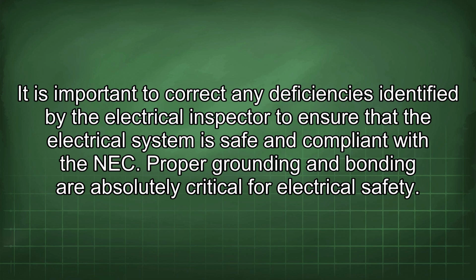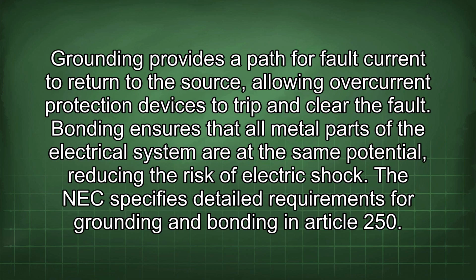Proper grounding and bonding are absolutely critical for electrical safety. Grounding provides a path for fault current to return to the source, allowing overcurrent protection devices to trip and clear the fault. Bonding ensures that all metal parts of the electrical system are at the same potential, reducing the risk of electric shock. The NEC specifies detailed requirements for grounding and bonding in Article 250.